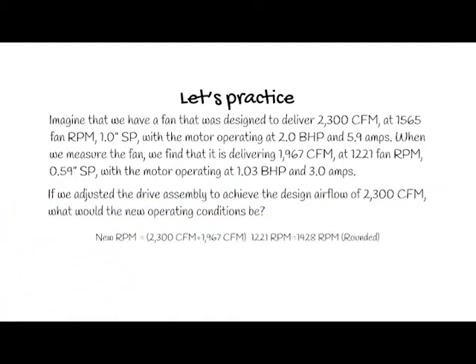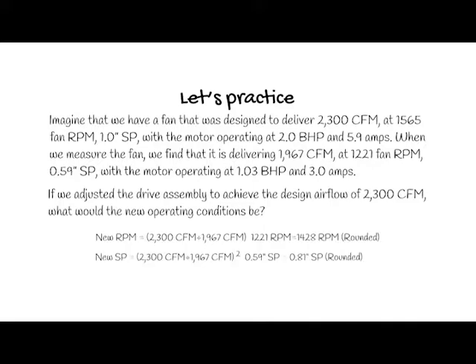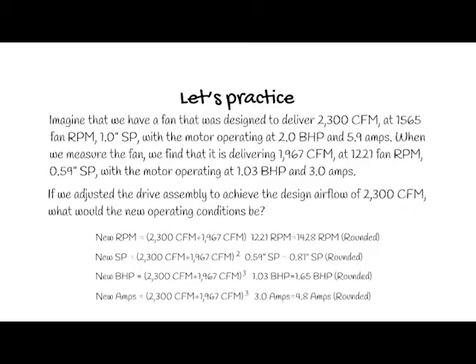The new RPM would be 1,428. The new static pressure would be 0.81 inches. The new brake horsepower would be 1.65, and the new amp draw would be 4.8.